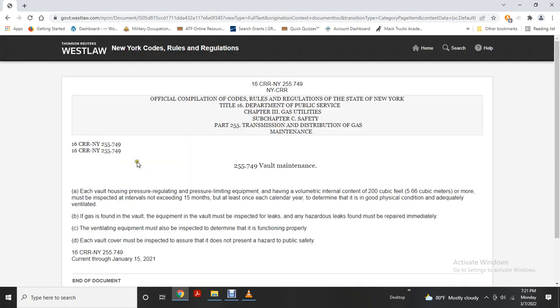Vault maintenance. Each vault housing pressure regulating or pressure limiting equipment that has a volumetric internal content of 200 cubic feet or more must be inspected at intervals not exceeding 15 months, but at least once each calendar year. The vault must be in good physical condition and adequately ventilated. If gas is found in the vault, the equipment and vault must be inspected for leaks. Any hazardous leak found must be repaired immediately.